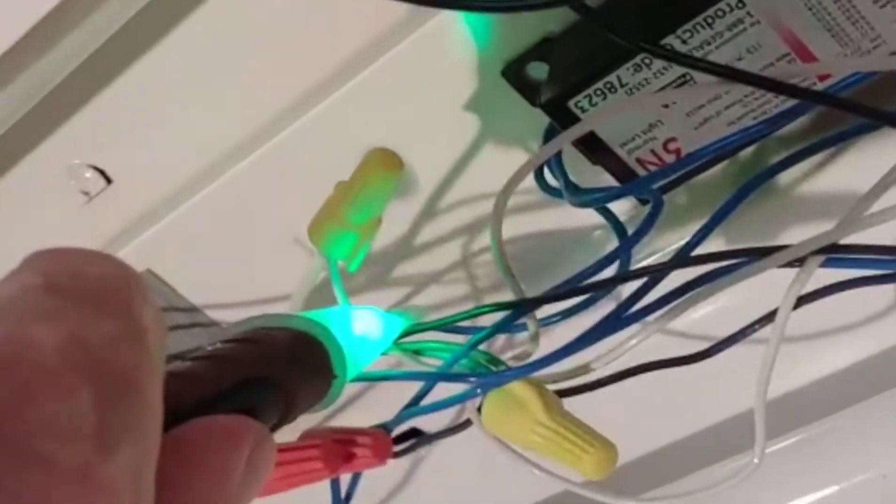Then we cut the wires. This is why I like the double end ballast. It's very easy. There is a single wire going to one end. I'm gonna use it to hook it up to the hot on the pins. And then the neutral will go to the other one. They're black, so it really makes no difference, I notice. I'm gonna use my voltage sensor. As I see, this one is the hot. I put a cap on it. The neutral is correctly wired, so right now it's very safe to work. This is the only power present in the fixture. Everything else is disconnected.